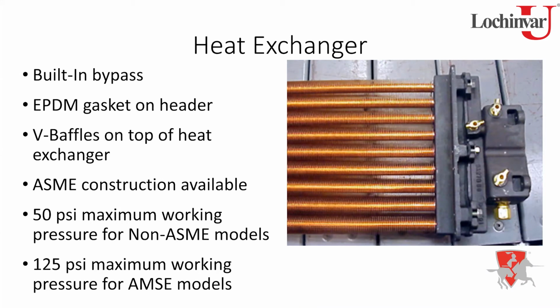Now, the heat exchanger itself will use a standard two glass line headers. So you have that rear header, which will be a glass line cast iron, as well as the front header, if you will, that front attachment. The removable header, that's going to be your difference, whether it be cast iron, glass lined, or the polymer.